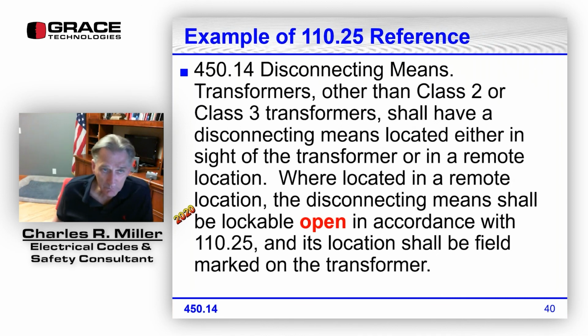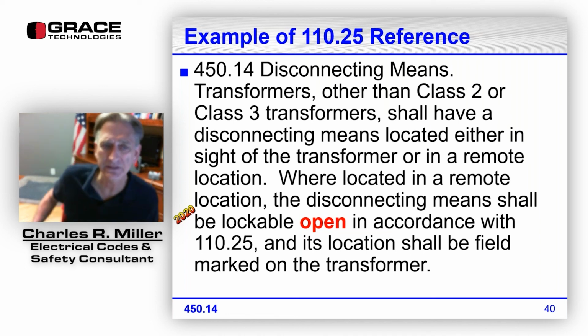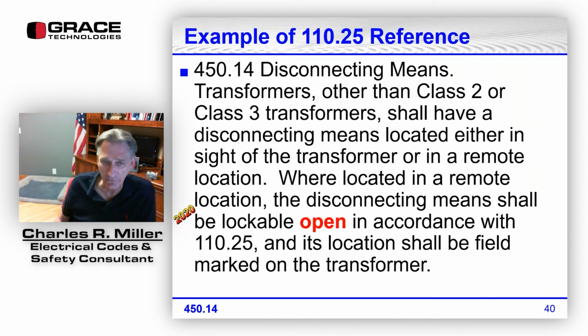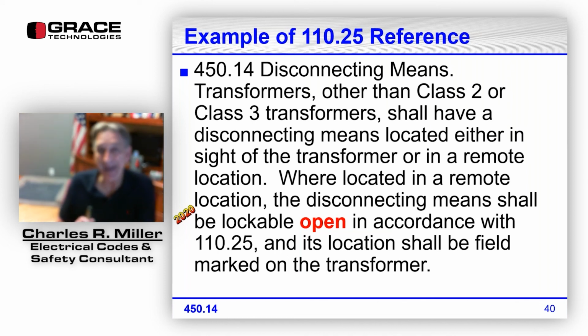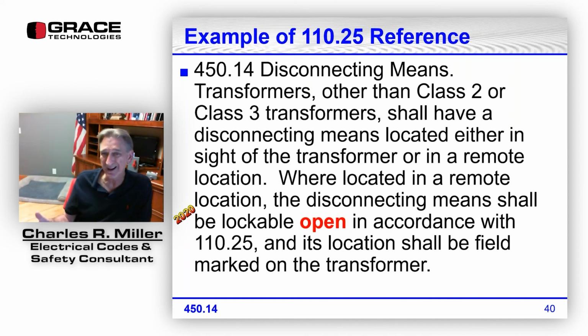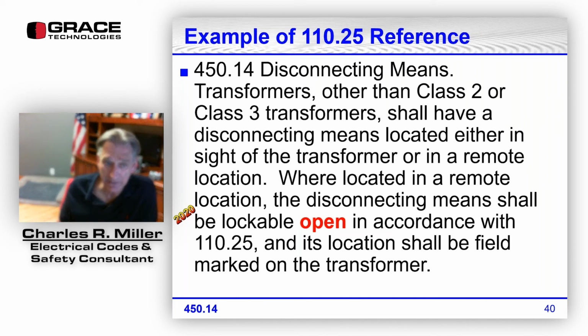Let's look at an example. Article 450 for transformers. 450.14 disconnecting means. It says transformers other than class 2 or class 3 transformers have to have a disconnecting means located either in sight of the transformer or in a remote location. Or it has to have a disconnecting means, period. It can be within sight of the transformer, which a lot of them are, but it doesn't have to be within sight of the transformer. If it's not within sight, it goes on to say where they're located in a remote location, the disconnecting means should be lockable open. That was really understood, but that wording was added for the 2020 edition.